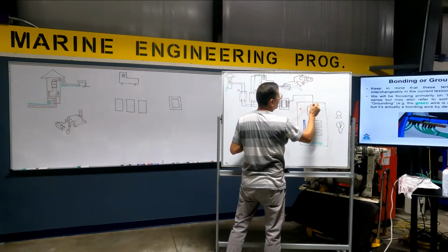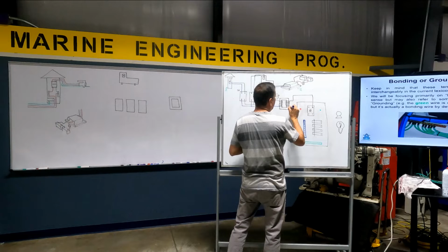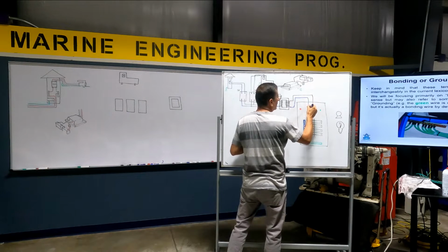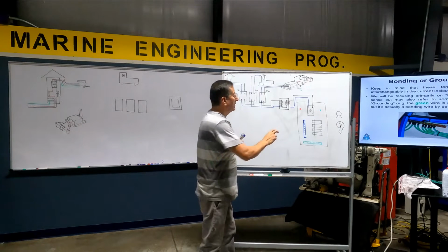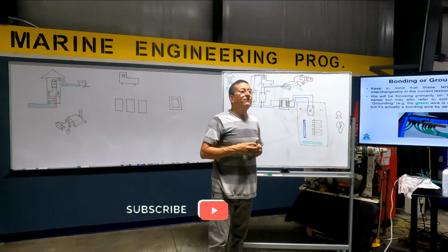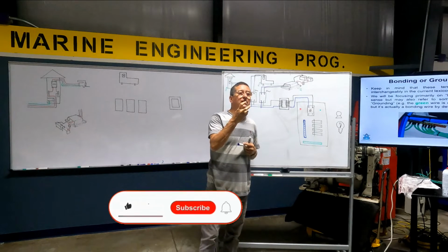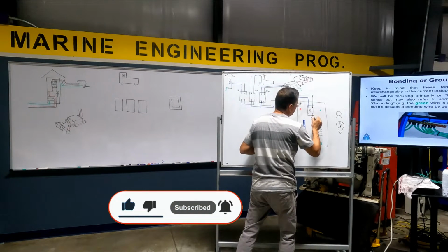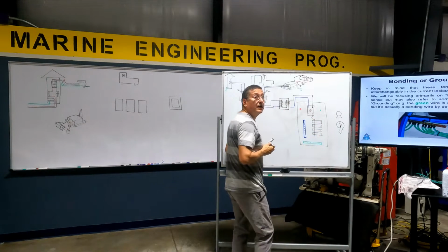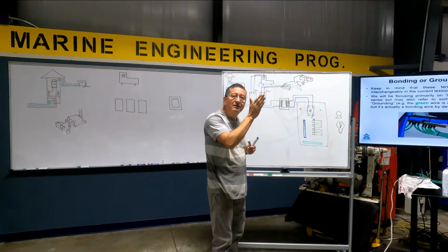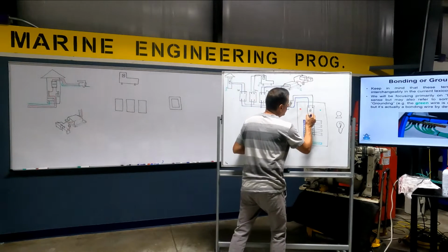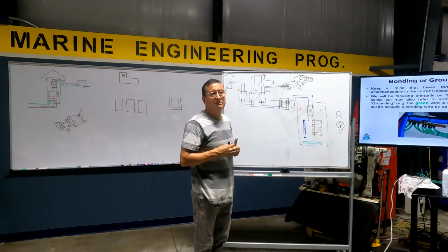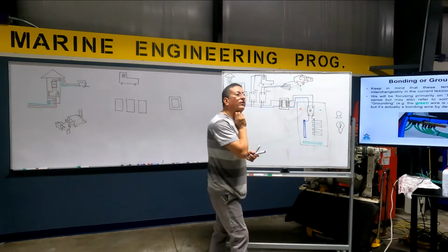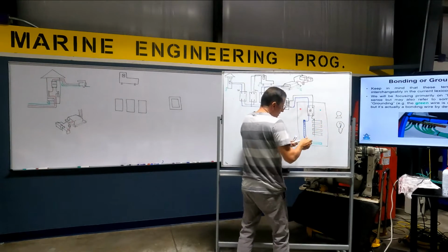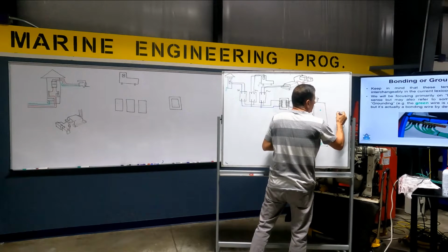And I have an input of hot line, and an input of neutral. This breaker is for single phase. A breaker for single phase only has two terminals, one for the hot line and the other one for the neutral. The hot line enters here in the hot bus bar. This is the hot bus bar that is common in all the breakers. And the neutral comes out directly into the neutral bus bar. And this is the ground. For example, I am going to connect here the motor for the pump. This is the fresh water pump, or any pump.